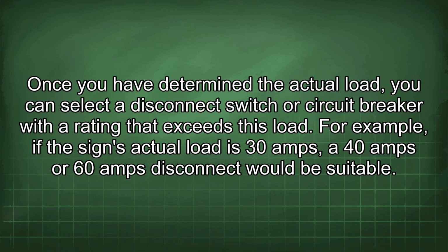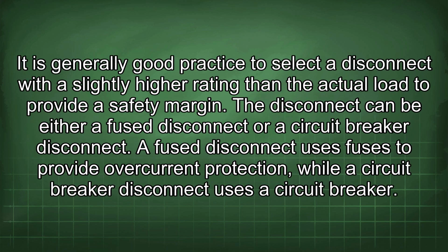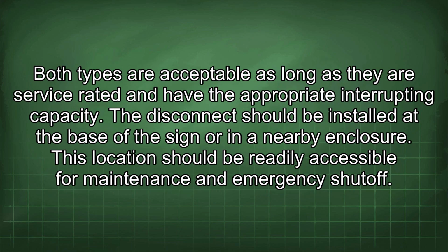Once you have determined the actual load, you can select a disconnect switch or circuit breaker with a rating that exceeds this load. For example, if the sign's actual load is 30 amps, a 40 amps or 60 amps disconnect would be suitable. It is generally good practice to select a disconnect with a slightly higher rating than the actual load to provide a safety margin. The disconnect can be either a fused disconnect or a circuit breaker disconnect. A fused disconnect uses fuses to provide overcurrent protection, while a circuit breaker disconnect uses a circuit breaker. Both types are acceptable as long as they are service rated and have the appropriate interrupting capacity.